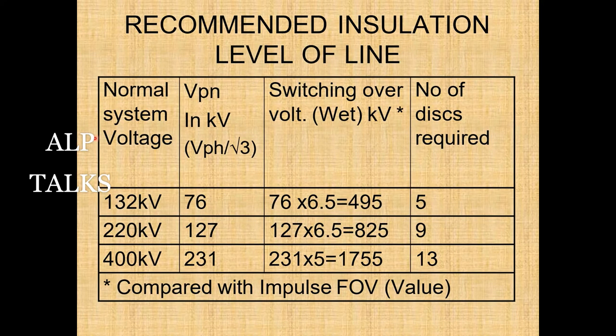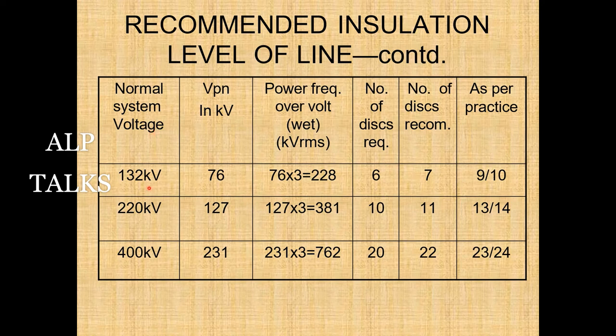Recommended insulation levels for transmission lines: for normal system voltages of 132, 220, and 400 kV, the phase-to-neutral voltages are 76, 127, and 231 kV respectively (dividing by √3). Switching overvoltage is generally taken as 6.5 times the phase voltage. For these voltage levels, the number of discs required based on switching frequency is 5, 9, and 13; based on power frequency (checked at 3 times), 6, 10, and 20 discs are required, with 1–2 additional discs recommended — giving practical values of 9–10, 13–14, and 23–24 discs.